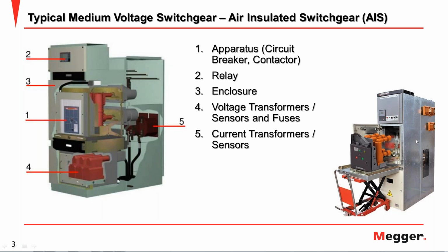You need to take out the breaker from the panel, and after that you need to connect this part. This part you need to arrange the position, maybe put it inside a little bit, and put this control terminal to the system. So we still use the voltage and circuit from the system. You only need to take out the breaker a little bit to be able to connect the main contact to the breaker's main contact. Normally like that. Okay, yeah, thank you, bro.